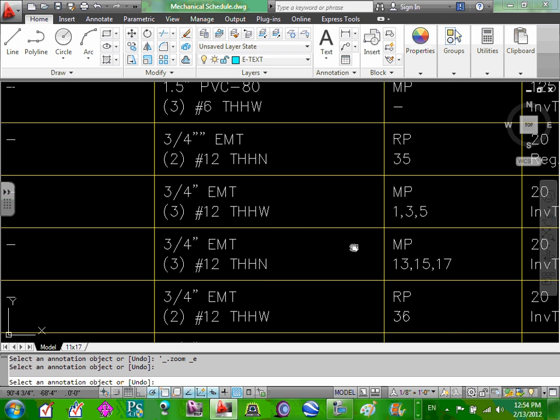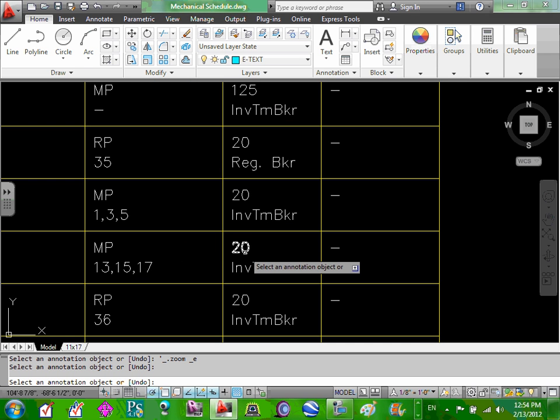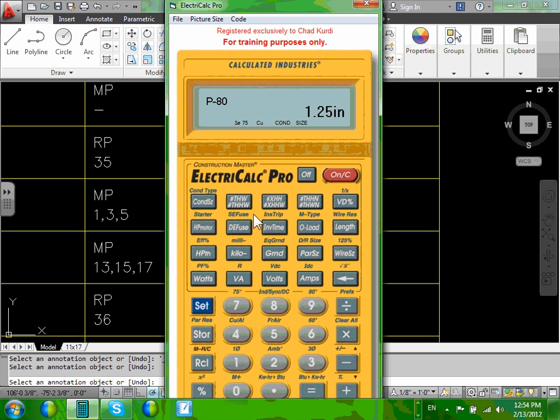Then you go to the mechanical room where it's fed. Oh, circuit breaker. Now this is a motor. Let's go do that one for circuit breaker, guys. Here's my 2 horsepower motor. And the voltage, what was the voltage again? 208. And here's the full load amps, 7.5, right? And I need the conductor wire size. It's telling you number 14, but we decided we're not going to use number 14, number 12.